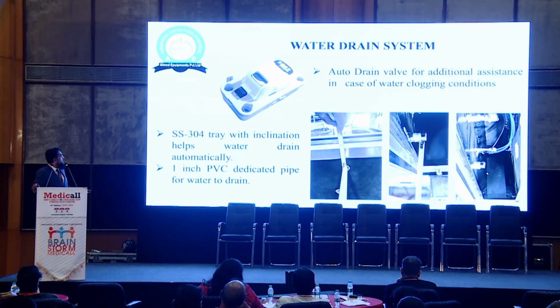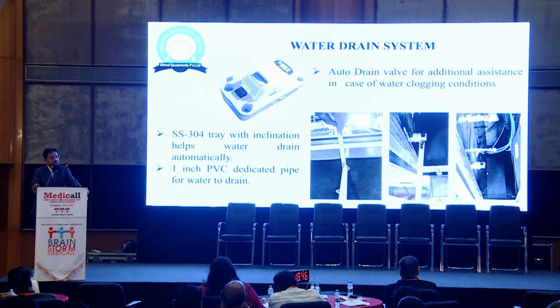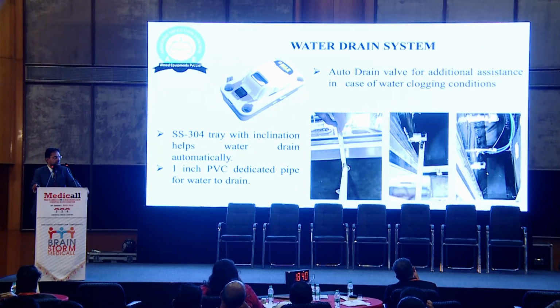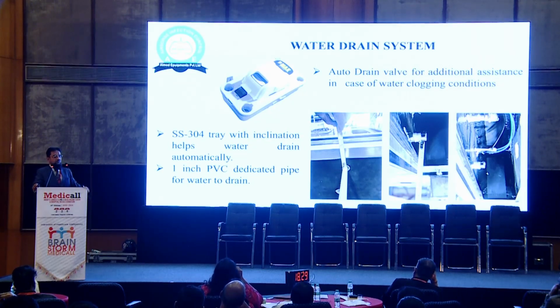Apart from that, we have given the auto drain valve. After every 10 minutes, for 1 minute it will start, and it will drain down all the water from the tray. So this is the additional safety system we have given. So there is no chance of water coming from the tray of the cooling coil.